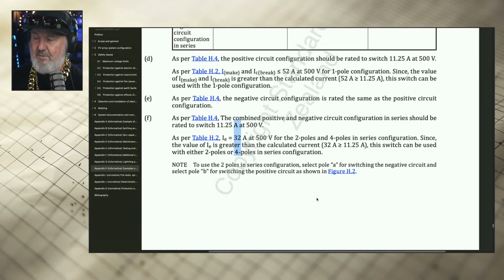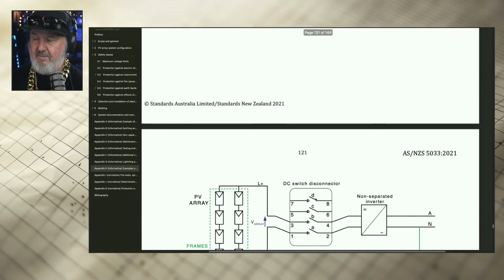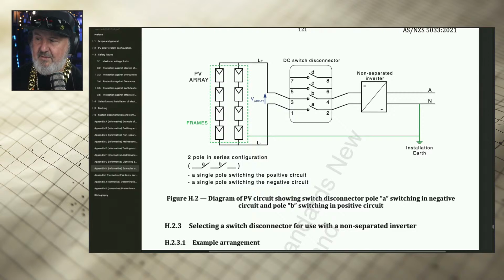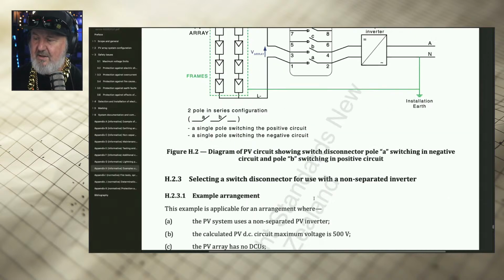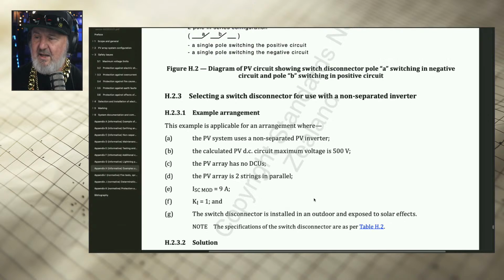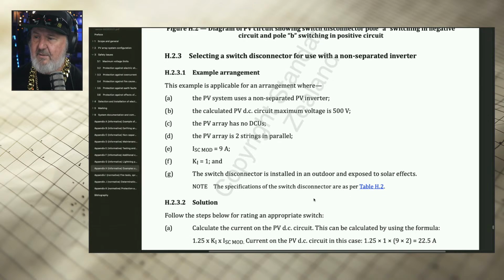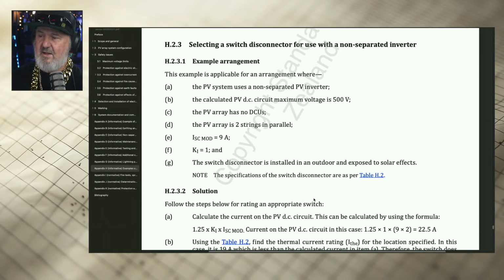Okay, last example. And that's a diagram of that configuration, by the way. The last example is, once again, another transformerless inverter. And this one is a little bit different. We've got 2 parallel strings. So everything else is similar to the previous example, except instead of 1 string, we've got 2. And we've got the same 9 amp modules, so 9 amps. So we're just trying to pump more current into that same MPPT of the inverter.